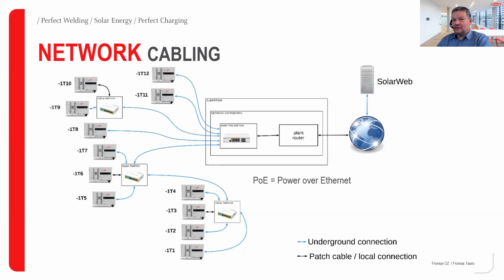The main advantage of this connection is that if one device fails, the whole system doesn't stop, because of the star topology in which the inverters are not connected in series. Only the inverter which failed stops producing, and the rest of the inverters keep running. This topology is also advantageous in case there is a requirement for reduced feeding to the grid, where a PV plant controller is used on that system.